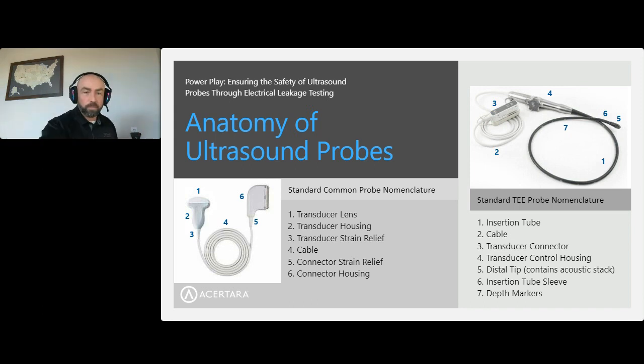So the patient interface is the transducer lens. This is typically a softer material when you're looking at GE probes. It's about the consistency of human tissue, very similar in how that feels, maybe a little stiffer. Some transducer manufacturers actually use hard lenses. That's less common today. The second piece you see there is the transducer housing. That's what people use to hold on to while they're actually doing the image. It protects the electronics inside, and it gives us a surface that is suitable to be disinfected. These probes also typically go through a high-level disinfection using a wipe. There are some automated solutions, and that's generally how it's handled.